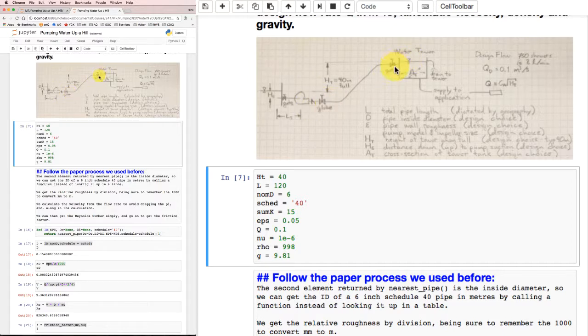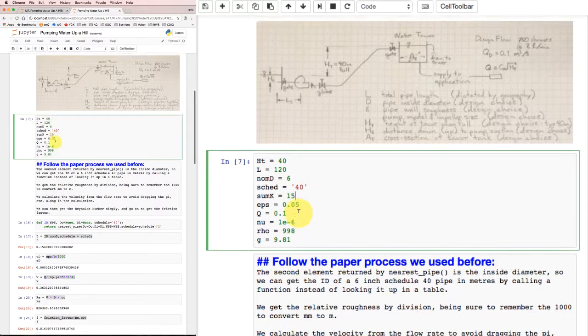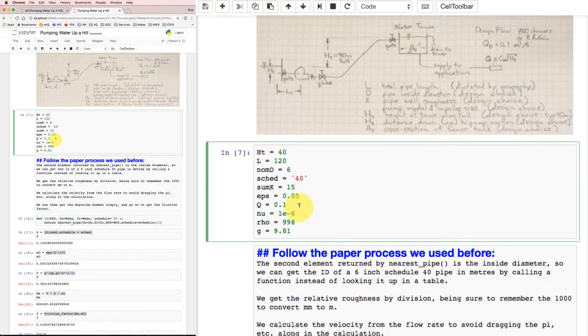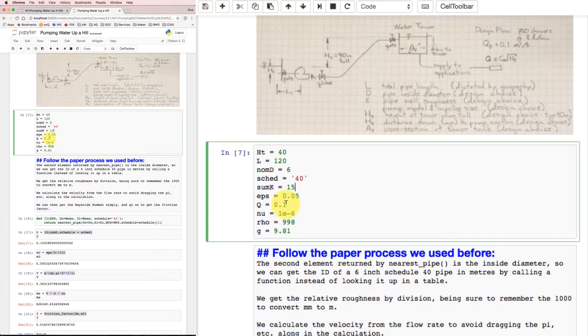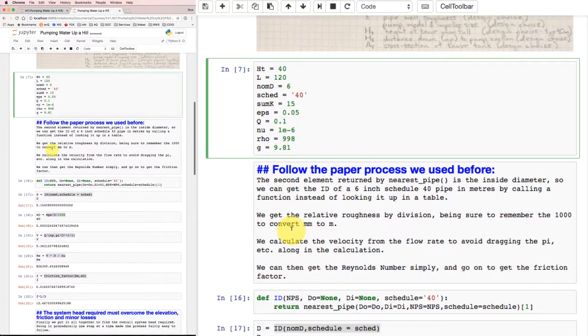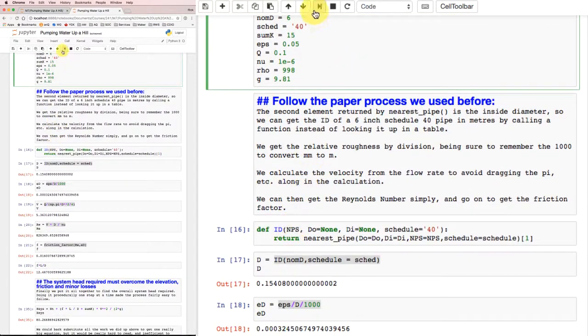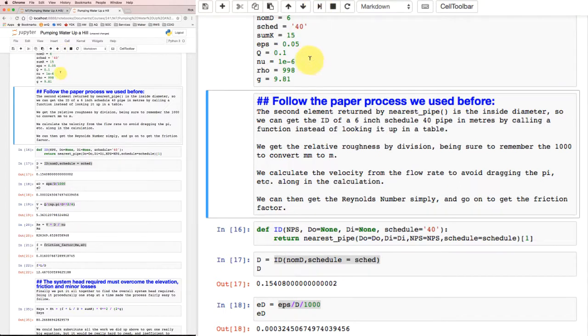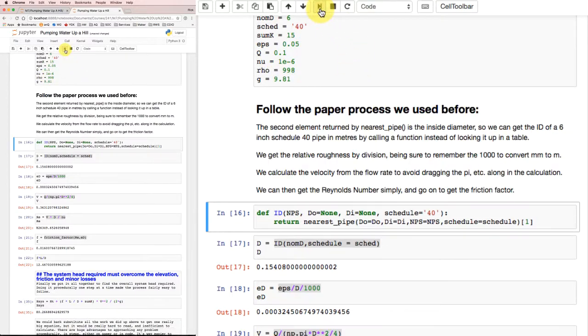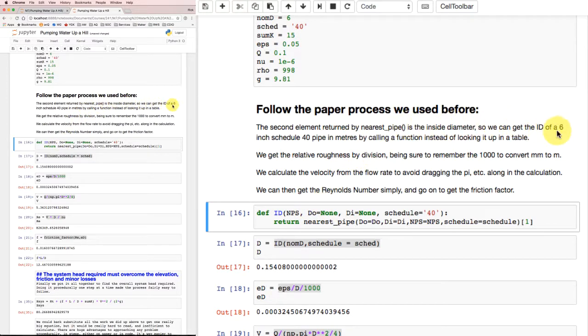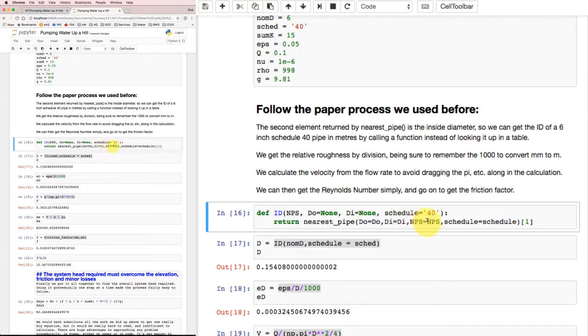The value I got before for the sum of the K factors for everything - the gate valve, globe valve, the other gate valve, the exit, the entrance - wound up with sum K equal to 15 and a roughness of about 0.05 millimeters. My design flow rate is 0.1 cubic meters per second, kinematic viscosity of water is 1 times 10^-6 meters squared per second, density about 998 kg/m³, and gravity is 9.81. I'm going to follow the paper process. Better make sure I run that cell and assign all those values. And I'll format this cell.